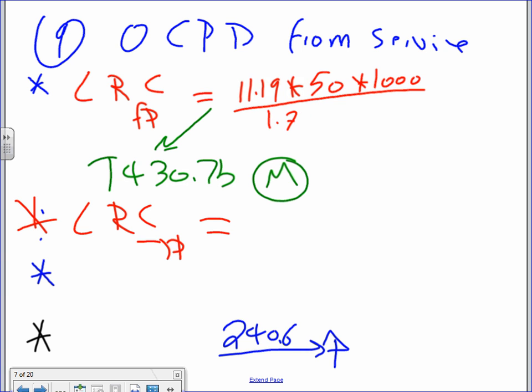Divided by 1.73. Derek or somebody, what's the voltage of this system? 480, thank you. So divided by 480, and that will get you 674 amps. So that's my amp. Now this is the fire pump. Right underneath it is the jockey pump. We need to do the same thing for the jockey pump.